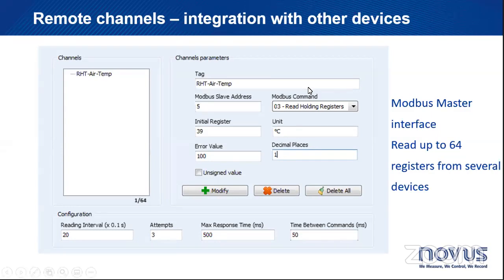First of all, is a tag. So I give a name to that channel. Then I will let the FieldLogger know what is the Modbus address. For those who are familiar with Modbus, you know that every device on a Modbus network has a unique ID, a unique address. So that unique address is the Modbus slave address. Then you select the Modbus command. By default it is 03, reading holding registers, but the manufacturer's manual is generally where you will find what Modbus command it answers to.